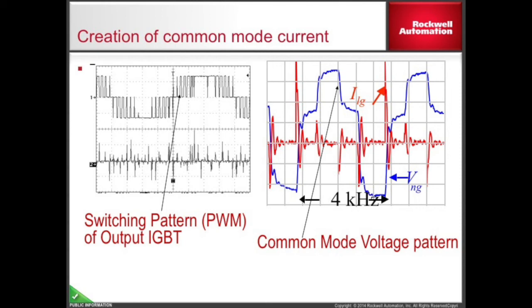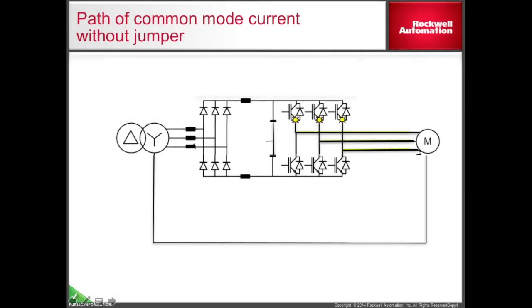The magnitude of the common mode current goes up with motor lead length. Here, the common mode current path is shown without the PEB jumper installed. Without the PEB jumper installed, the current will take an uncontrolled path back to the corresponding IGBT, selecting the least resistant path all the way through the transformer, back up through the line, and to the drive.